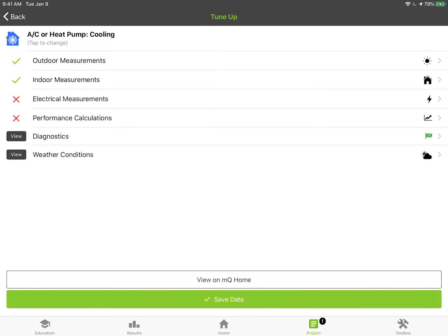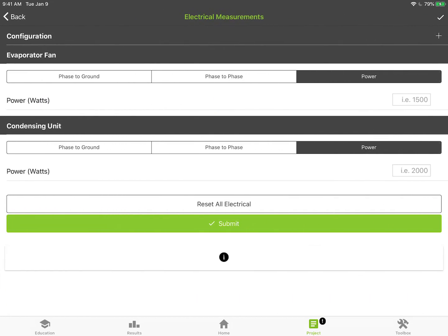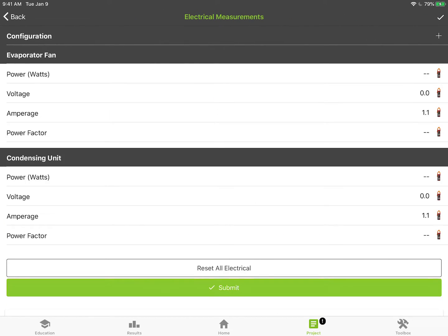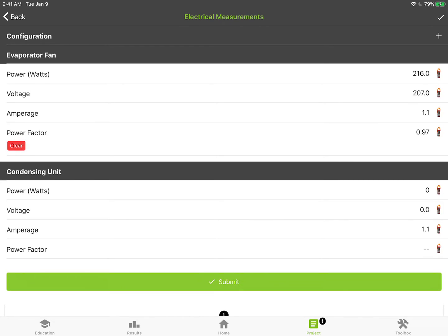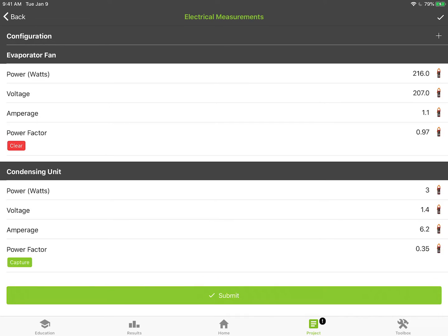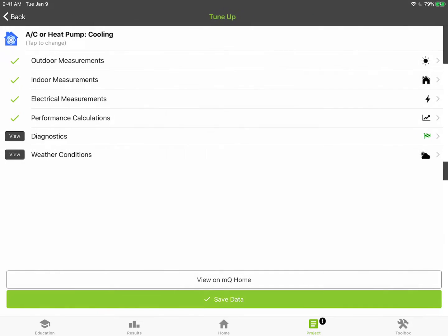The next thing I need to do is just turn on my electrical meter and grab those. I'm going to tap on electrical and then you'll see the meters turned on and connected. We're going to connect first on the evaporator fan and we'll get the evaporator fan watts. I'll just hit capture there and then we're going to move it over and measure on the condenser. Here's our condenser fan watts. We'll hit capture and then all the readings are in. You just take them one at a time and they're locked in there. We'll hit submit.